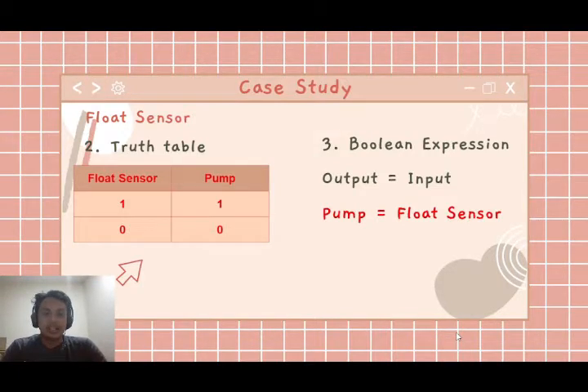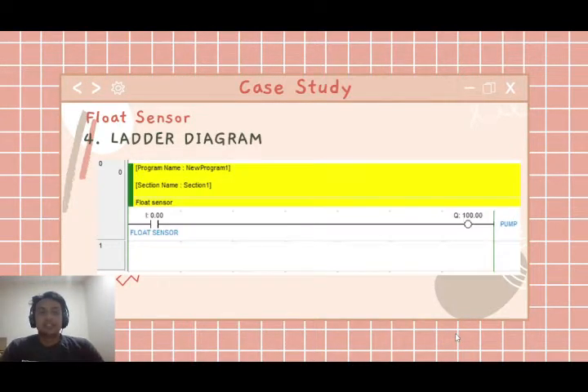For the float sensor, when the condition is high level, the pump will operate, and if the float sensor is in low condition, the pump will also be zero, no operation will be set. Okay. After that, we must do the Boolean expression. Output is equal to input. The pump is equal to float sensor. Okay, this is the ladder diagram for the float sensor application in the question. First, we have the LD, the float sensor I equal to 0.00, and we have the pump Q100.00.